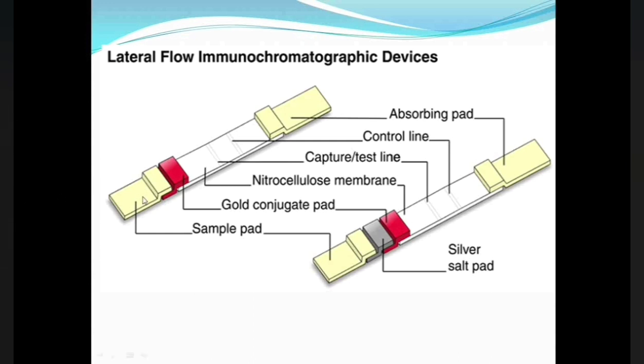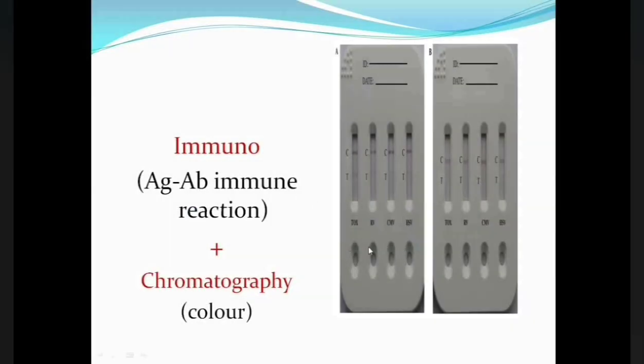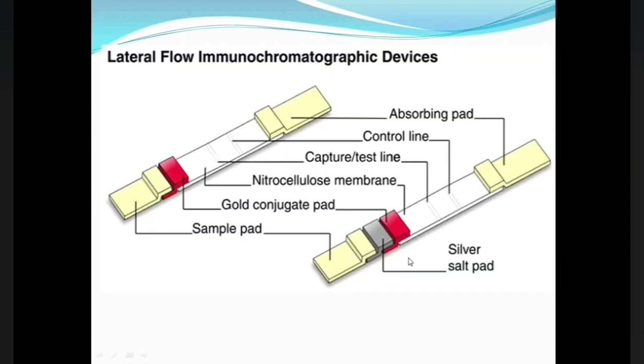The first and foremost part is the sample pad, upon which the liquid sample is dropped. It is called the sample pad because the sample is dropped onto it, and in the outer cassette covering it is present in the form of a window. Adjacent to the sample pad is the conjugate pad, in which we place the detector conjugate. The first step is putting the sample and the second step is putting the detector conjugate.